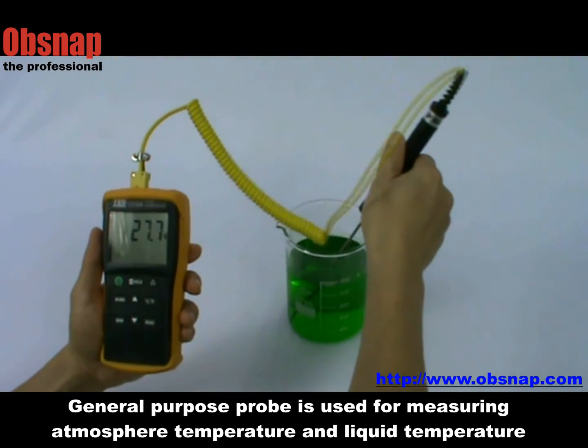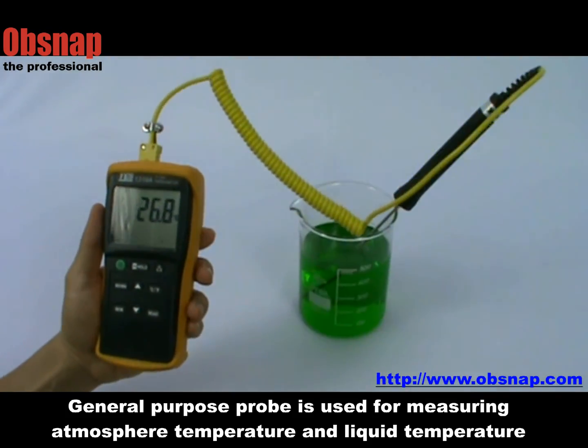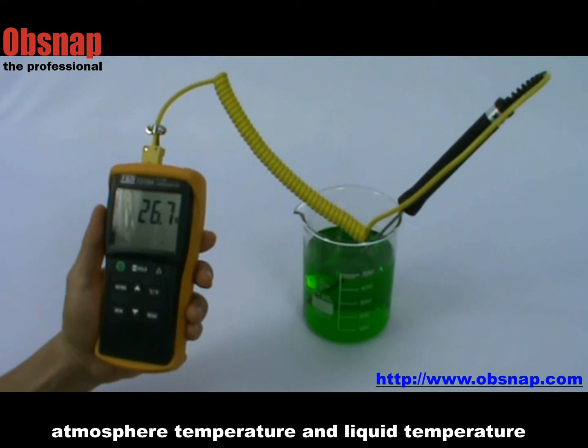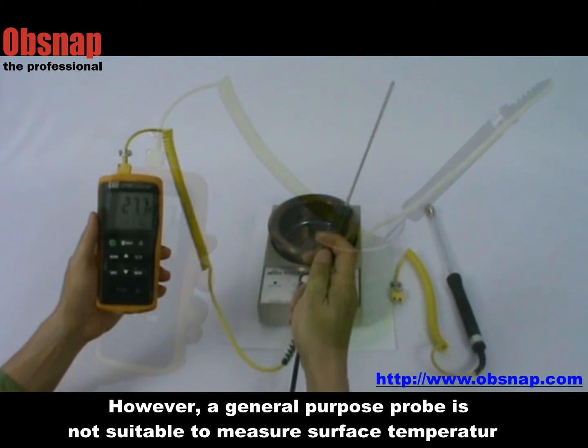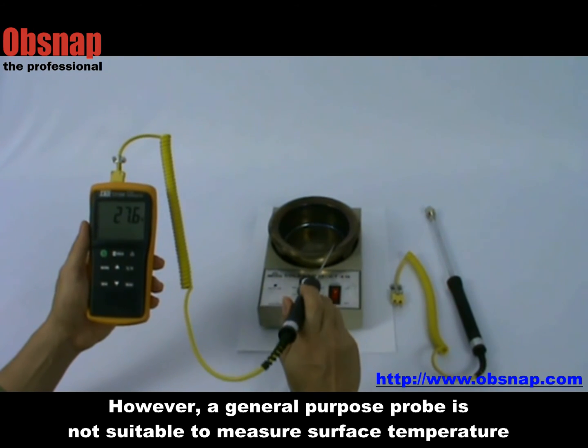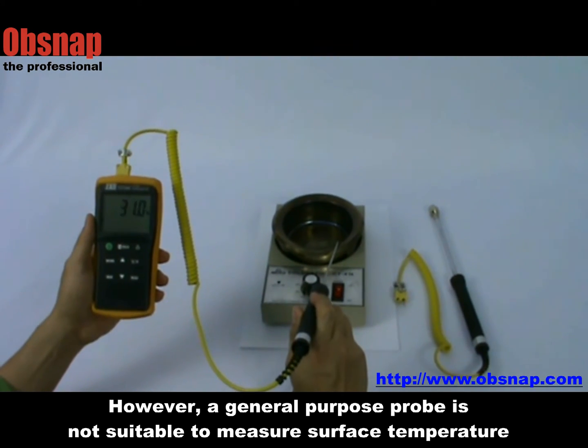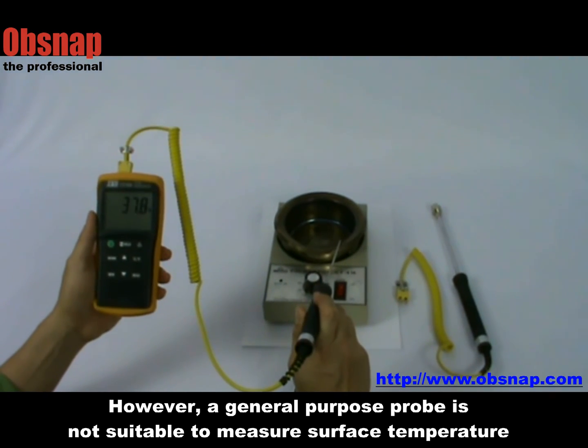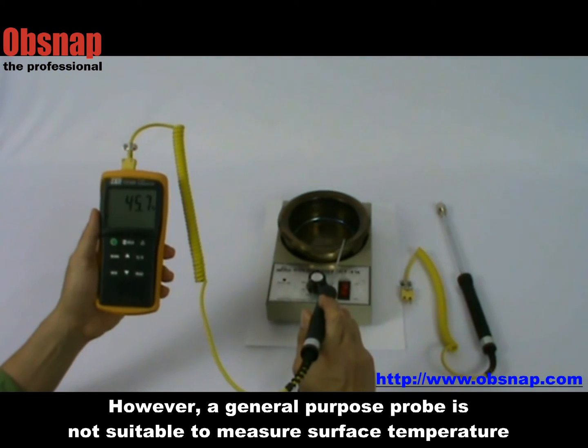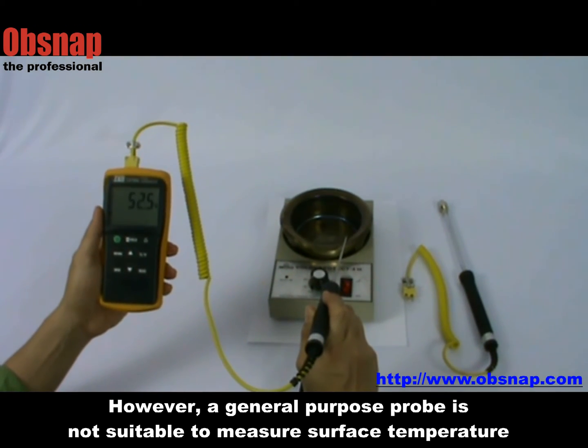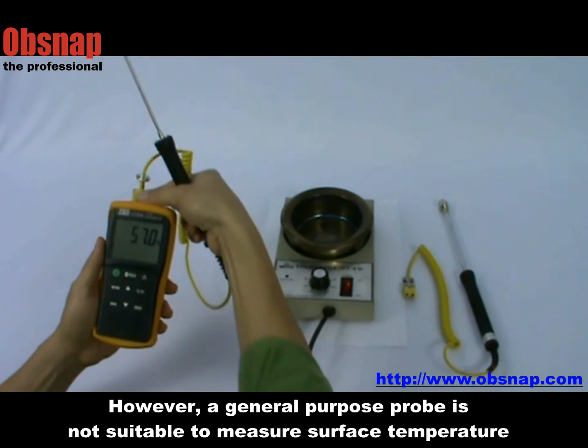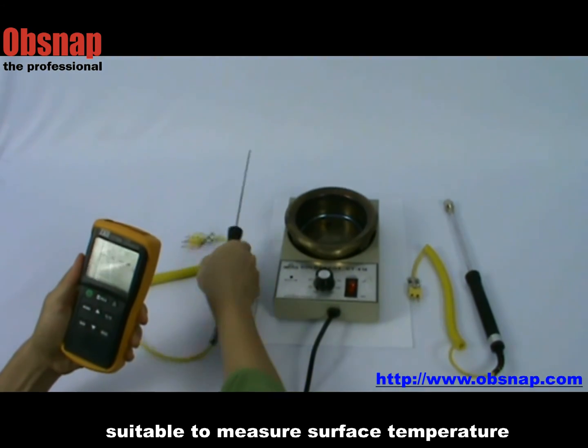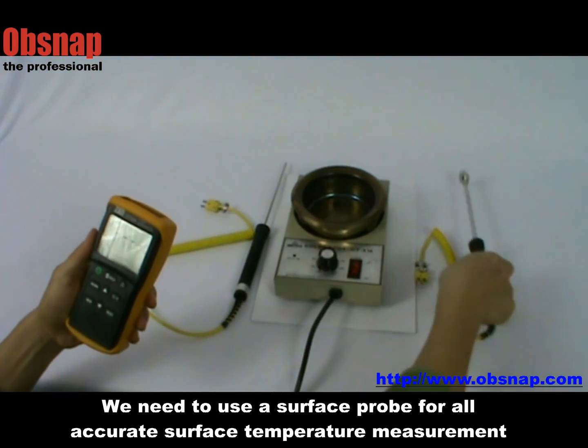The general purpose probe is used for measuring atmosphere temperature and liquid temperature. However, a general purpose probe is not suitable to measure surface temperature. It is because the contact surface is too small and not fully covered. As you can see, the response time is slow and the reading is lower than expected. We should change to the right probe.